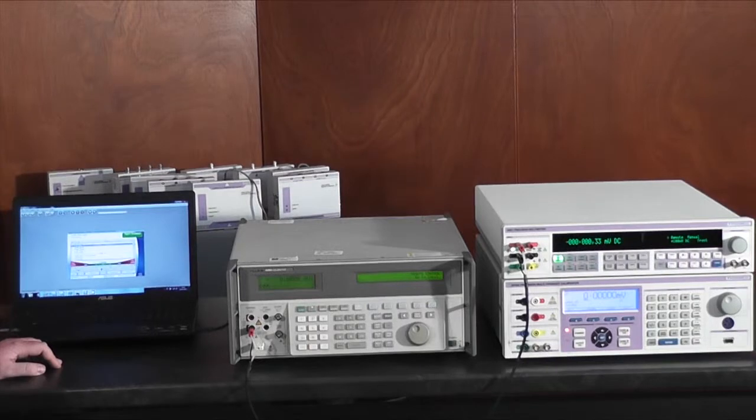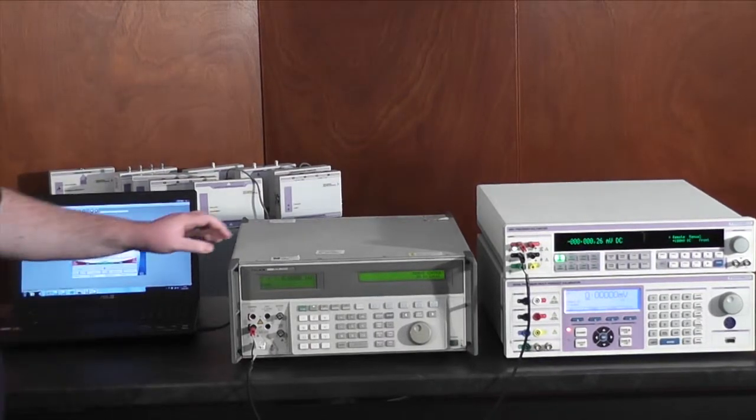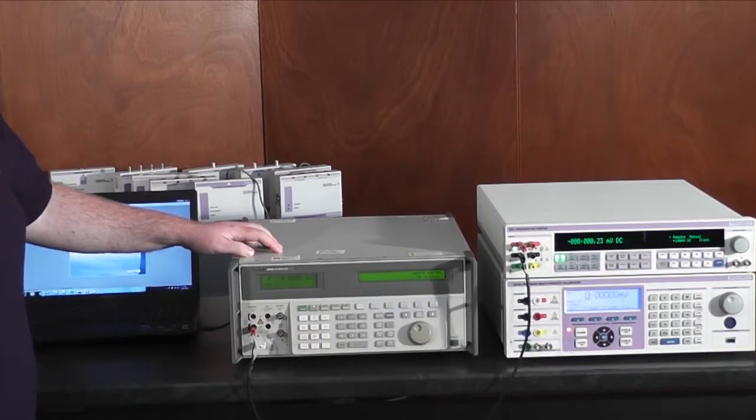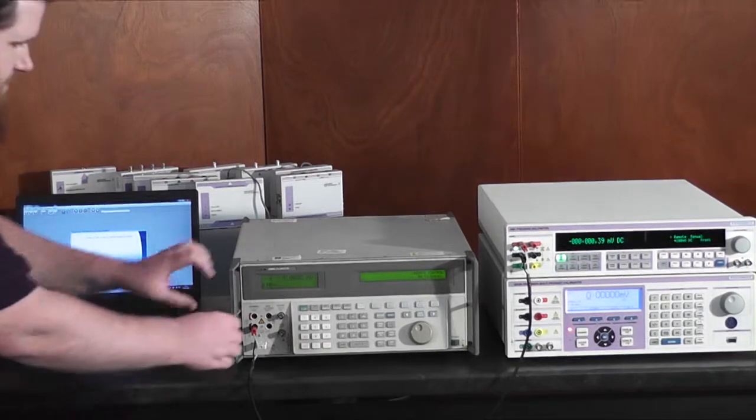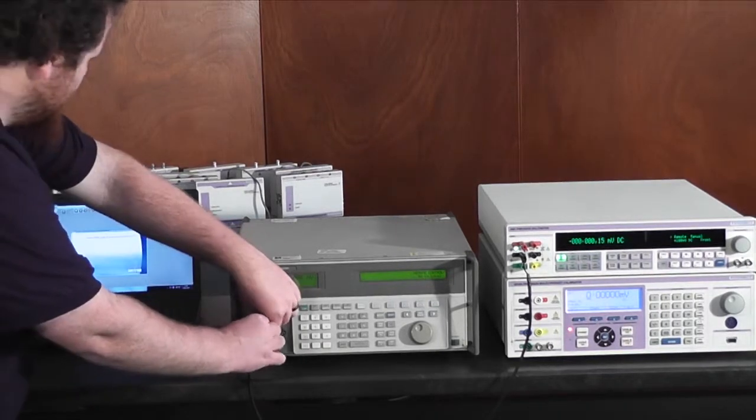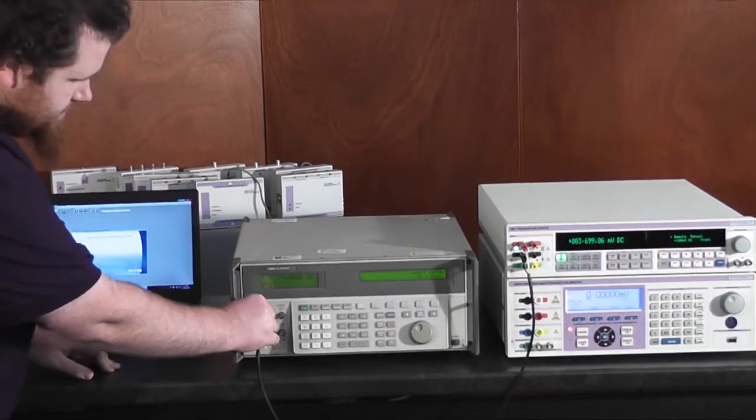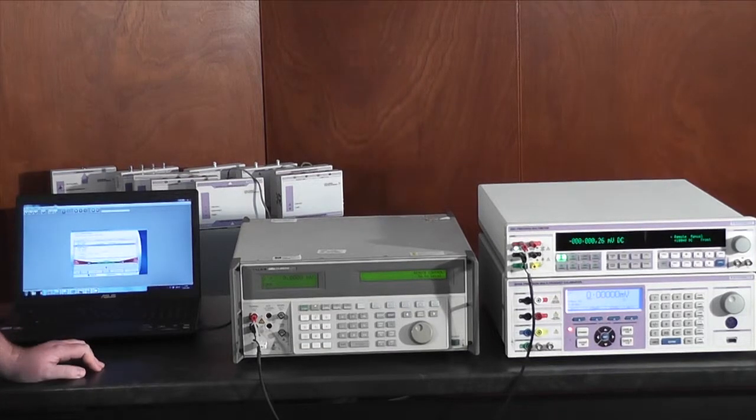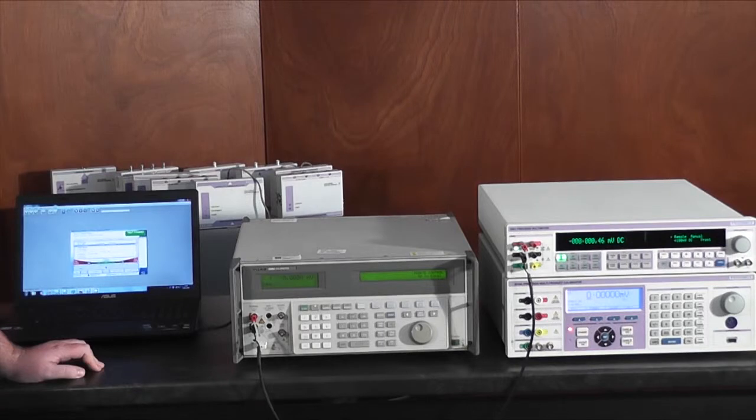ProCal is now automatically interfacing with both the UUT and the 8000 series. So once again another prompt and now fully automatic closed-loop verification is occurring.